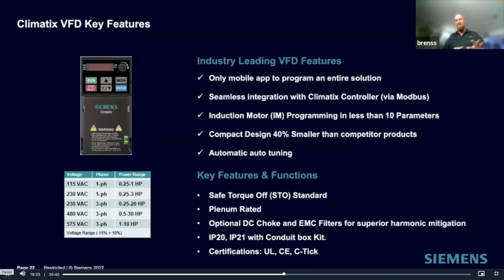Some of the key features are the safe torque off standard, the STO. This is where we don't have so much wear on the motors anymore. It's plenum rated, so you can mount this in the ductwork right at the unit. We have them mounted outside, everywhere inside RTUs. We have an optional DC choke and EMC filters if needed for superior harmonics. IP20 and 21 with a conduit box kit, and certifications are UL, CE, and C-Tick.